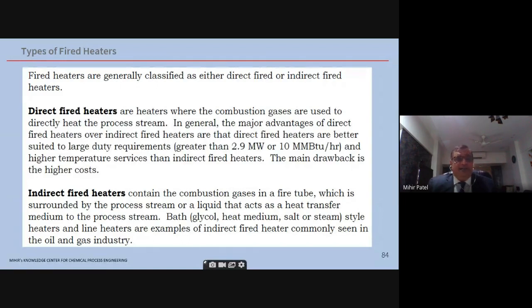These are called bath fired heaters. The fired heater has a burner, which passes the hot flue gases through a ducting and out through the exhaust. The flue gas duct is inside a water bath. Inside the water bath the process coil is also kept. This ensures that the process coil will never see a temperature above 100 degrees centigrade, so you are not overheating the process coil. That's why many times, let's say you have cryogenic propane, you are heating the propane. At the end, they have a water bath to heat it to atmospheric or ambient temperature, and they normally go with the water bath assembly, so that you ensure there is no overheating of the propane, etc.